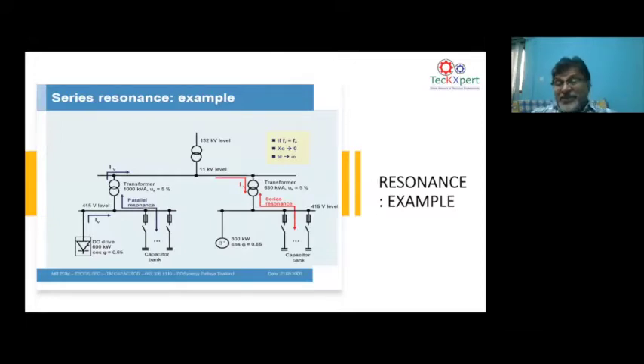Many times, when customers want to put capacitor banks in their plant, they think, okay, I don't have any harmonics, so I am going with plain capacitors. Now imagine the plight of this capacitor bank. You believe you have no harmonics, but you have not taken into account the harmonics your neighbor can produce, which can come into your factory and destroy your capacitor. So here again, both series and parallel resonance are important when you go for power factor correction.